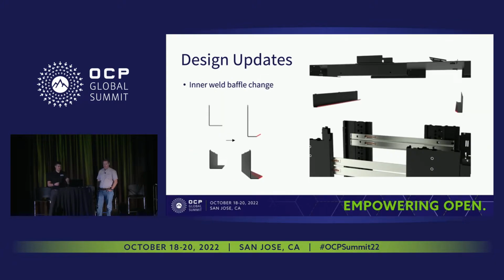So an additional update we did here is on the inner weld baffle, which, as you can see in the exploded view, actually gets welded into the top of the frame in the canopy. The primary reason for this baffle is obviously airflow, to prevent the hot air exchange over the top of the rack. And what we've done here is we've extended the depth of that to give it a tighter fit to the equipment to ensure airflow blocking.